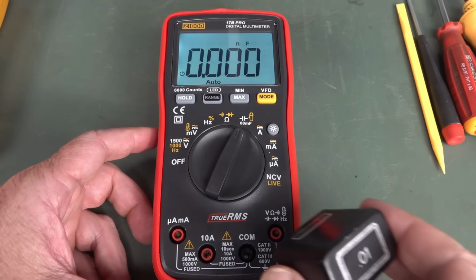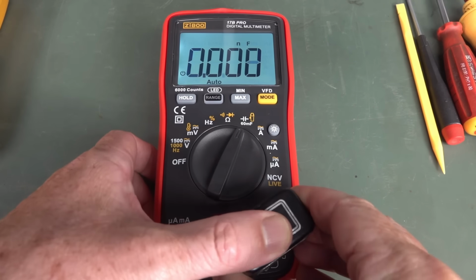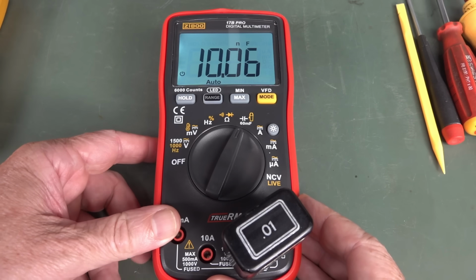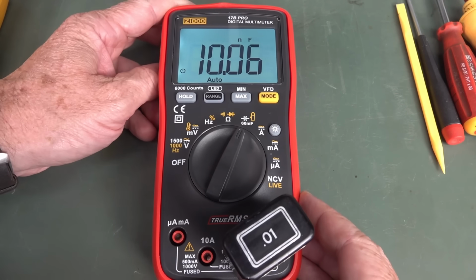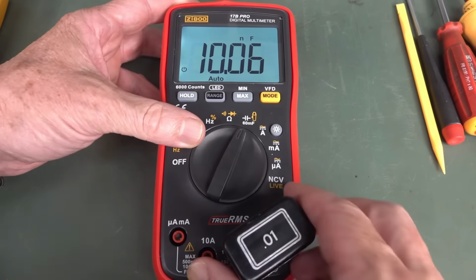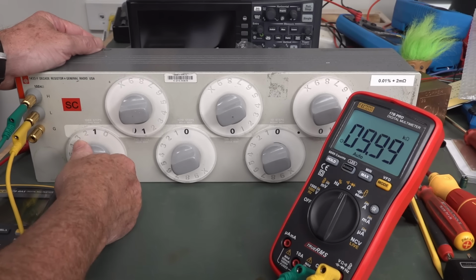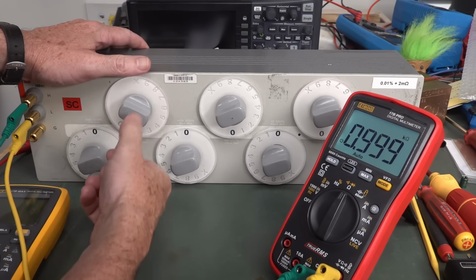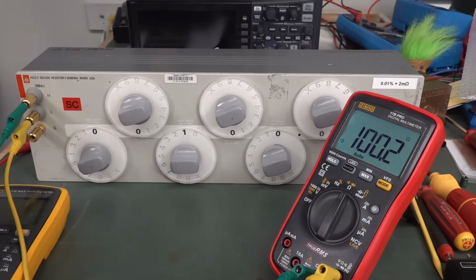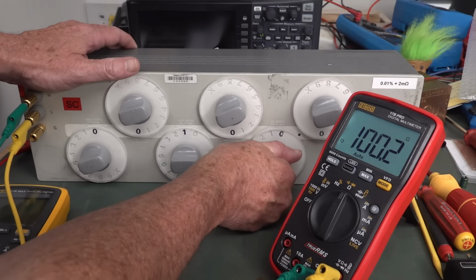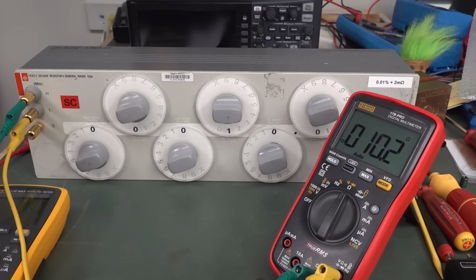Okay, reference capacitor, 10.06, 0.6% out, but well within spec. Resistance standard here, that's 1 LSD out, 1 digit out again, no worries. 2 least significant digits out there. And it looks like we're 200 milliohms out there, but that's the lead.